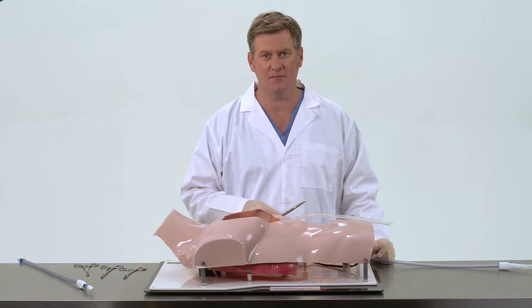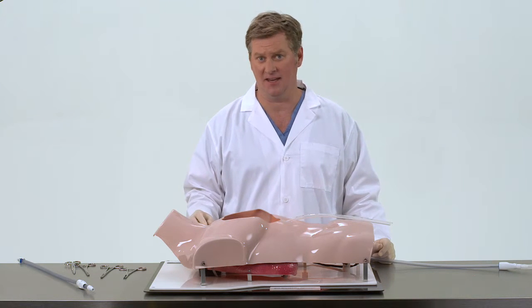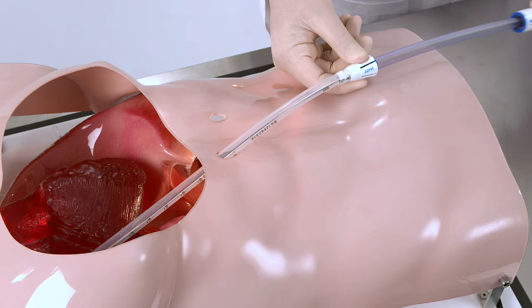The PleuraFlow System can be used in all standard drainage positions. However, when placing the chest tube the most important point is that the chest tube is not kinked or does not have a high degree of curves, so that the clearance wire and loop can easily enter and exit the chest tube.